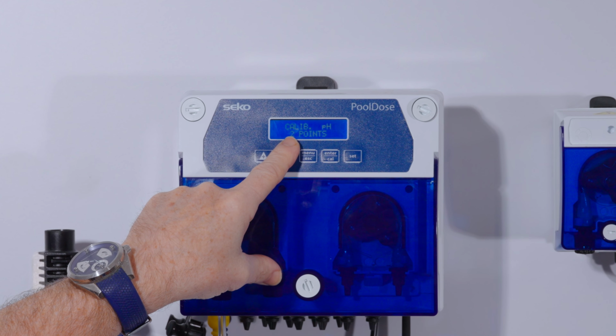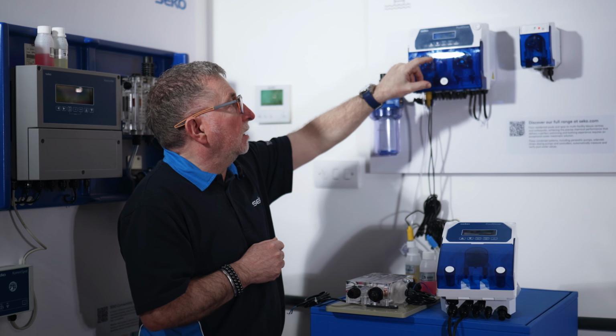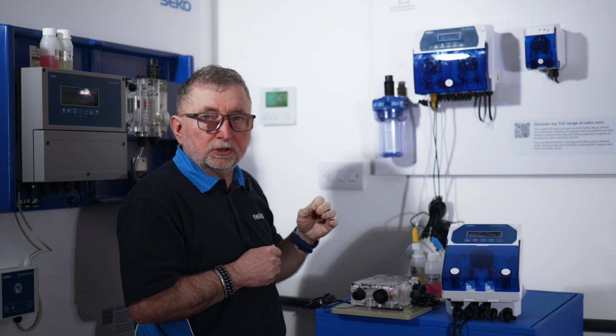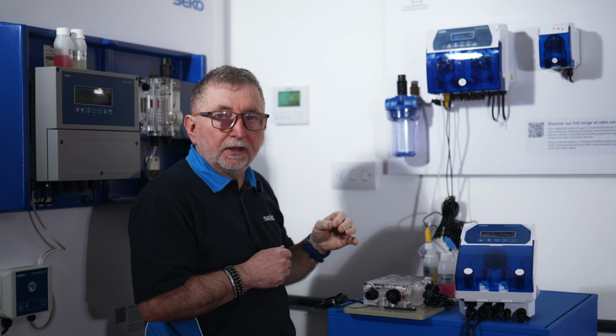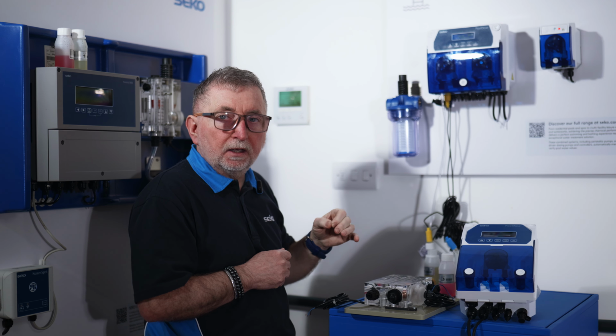Calibration. Here we have pH, which is 2 points. This is using 2 buffer solutions for a very accurate calibration. When calibrating the pH 4 will be the first one to fail. So to prolong the life of your probe, you can actually change that to a 1-point calibration and continue using the probe for a while. ORP is a 1-point calibration. We can also calibrate the temperature by reference or by a probe that's supplied with the system.